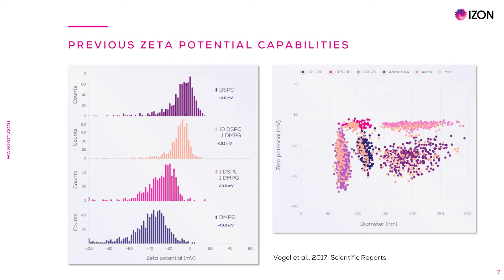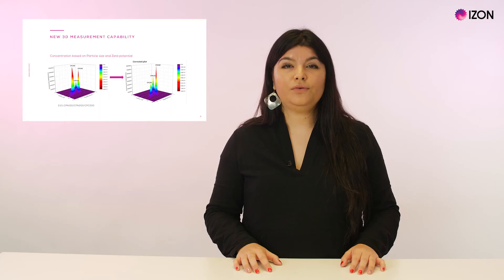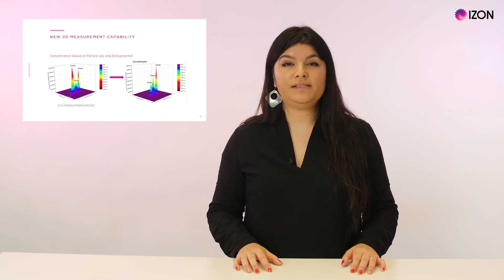In this plot, we can see that a pentamodal mix of particles of same sizes and different charge, such as charged carboxylated polystyrene CPC-100 versus bare polystyrene CPN-100, or magnetic particles versus magnetic particles with DNA, are well separated into different populations. So far, particle size and zeta potential can be determined simultaneously.